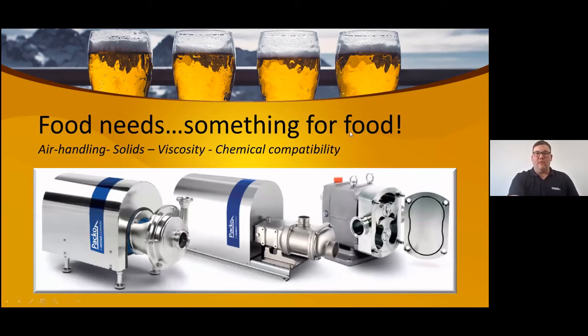So food needs something designed for food. Some pumps are designed with air handling capability, capable of pumping solids. So if solids need to be pumped, the correct pumps must be selected, with a big enough entry point and exit point, the suction and discharge and the eye of the impeller, so that the solids can fit through. Viscosity, I mentioned before. The more viscous the liquid, the more centrifugal pumps might not be the correct one, but an example is a rotary lobe pump for more viscous and sticky products. And also the chemical compatibility of the CIP, what chemicals are used in the CIP, and whether the materials of construction are capable of standing up to that.